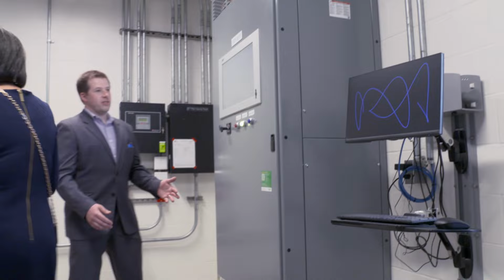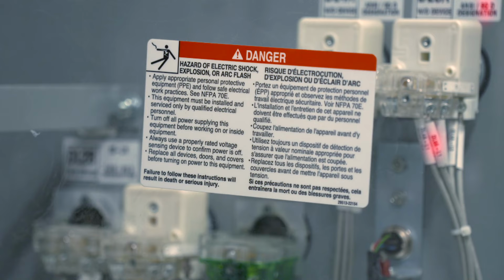The new system includes over 3,000 feet of underground, concrete-reinforced duct banks, and over 20 miles of electrical cables. You see the building that's behind me here, but something you don't see is all the underground wires that went from this building out, literally miles of insulated 15 kV wire that goes through vaults underground, distributed throughout the facility. All that nobody sees, but the distribution is done, and we now can control power for this facility with much fewer problems and much less risk.